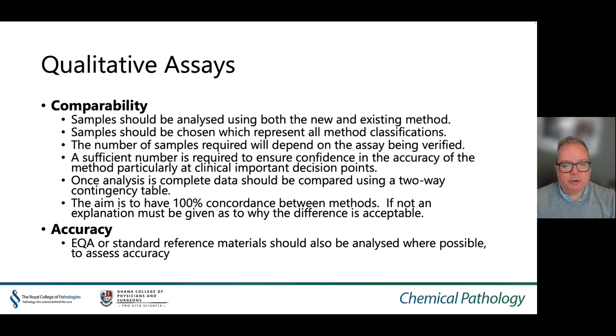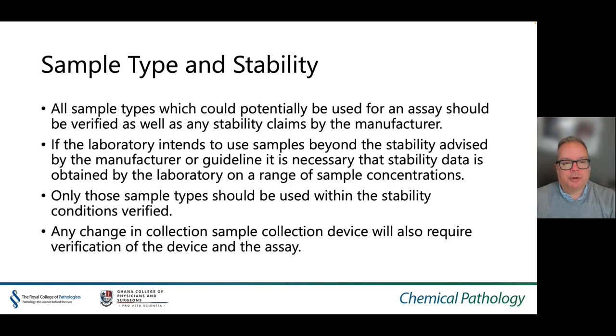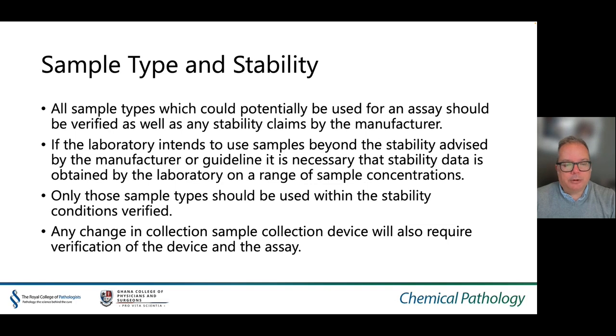Accuracy can be assessed using EQA or standard reference materials where possible. All sample types which could potentially be used for an assay should be verified, as well as any stability claims by the manufacturer. If the laboratory intends to use samples beyond the stability advised by the manufacturer or guideline, it will be necessary to obtain stability data on a range of sample concentrations. Any change in the collection sample device will also require re-verification of the device and the assay.